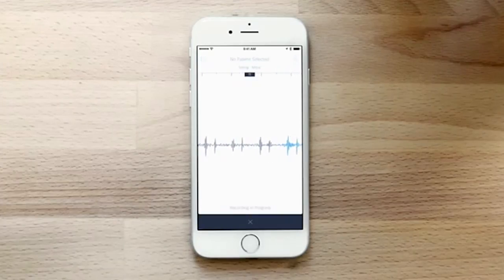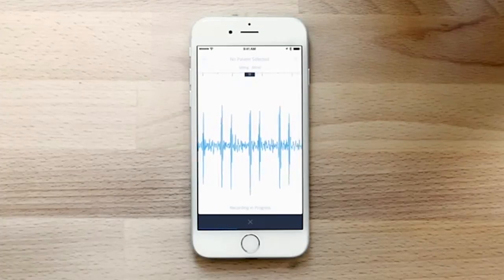So I have my stethoscope on and the app in my hand — do I have enough hands to do this? We tried to design it to be as user-friendly as possible, so you can use the app with a single hand. You could also just set the iPhone or iPad on a table in the operating room or exam room and use the Echo Core without even touching the app. You could also project it onto a larger screen for teaching, and we've seen physicians express interest in recording interesting murmurs to show their students at a future date — something totally impossible with an analog stethoscope.